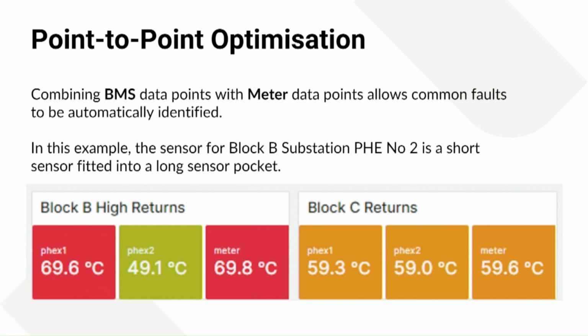This is a very quick, easy way of correlating your BMS data points with your meter data points to suddenly see a lot of problems on site at acceptance testing. We went straight for 30 sensors we knew were wrong the day after loading this up. No one even knew for 5 years these sensors were faulty - there was no way of knowing unless you started cross-referencing.